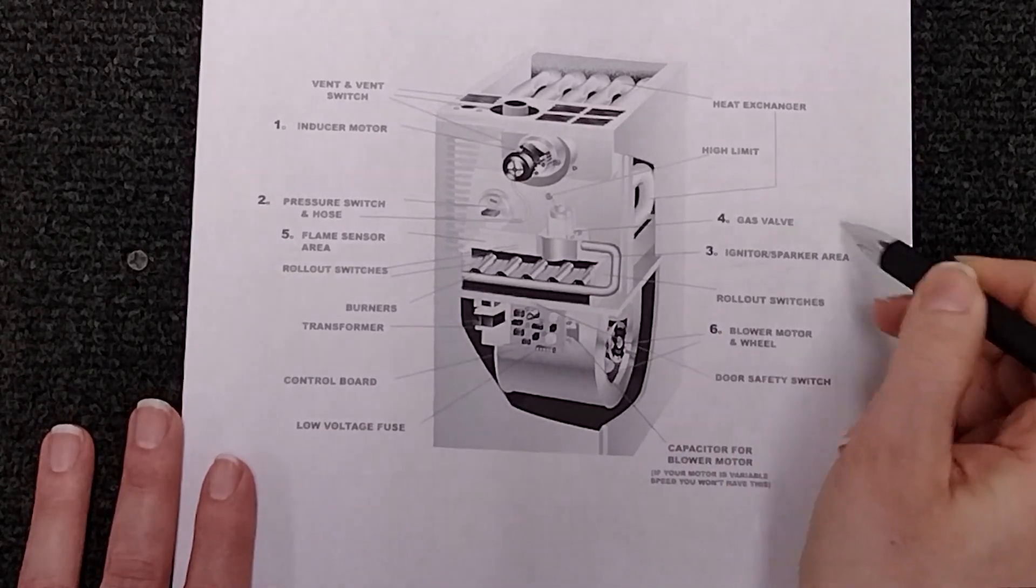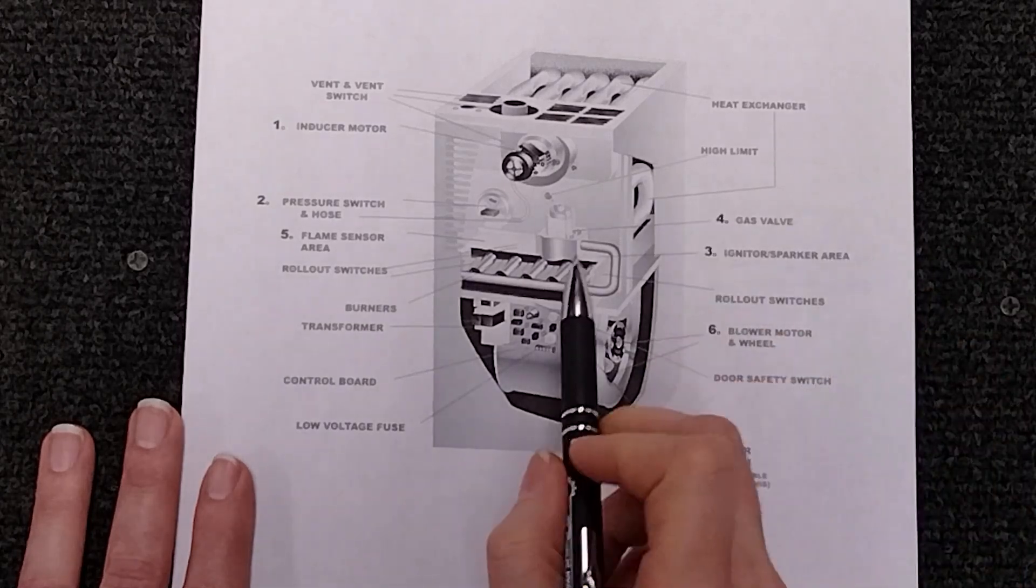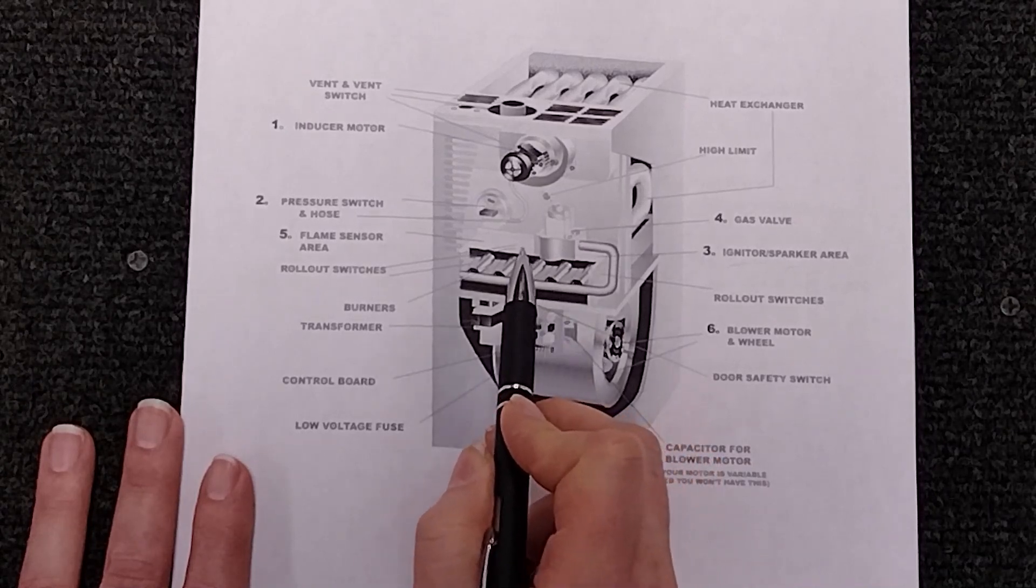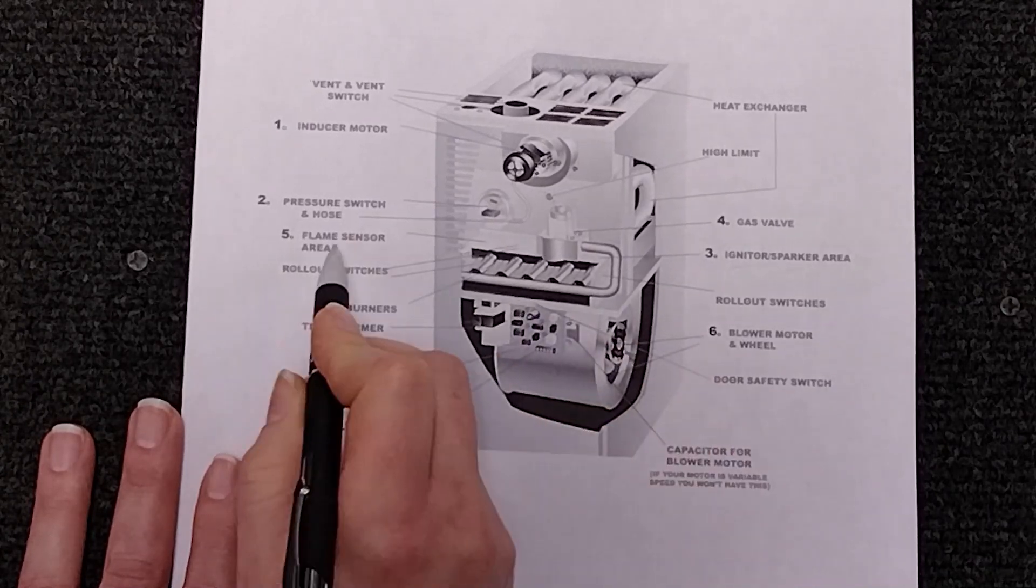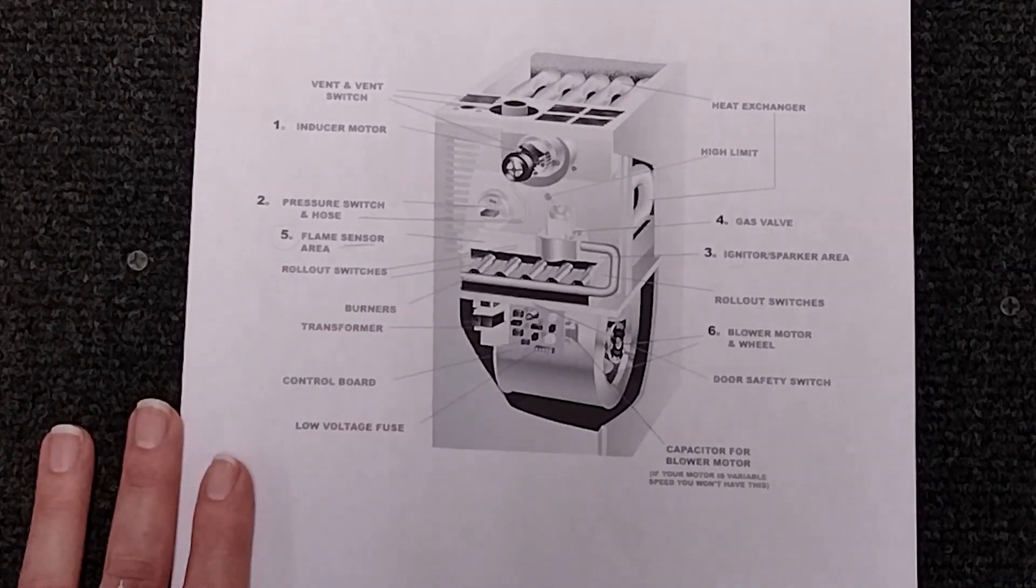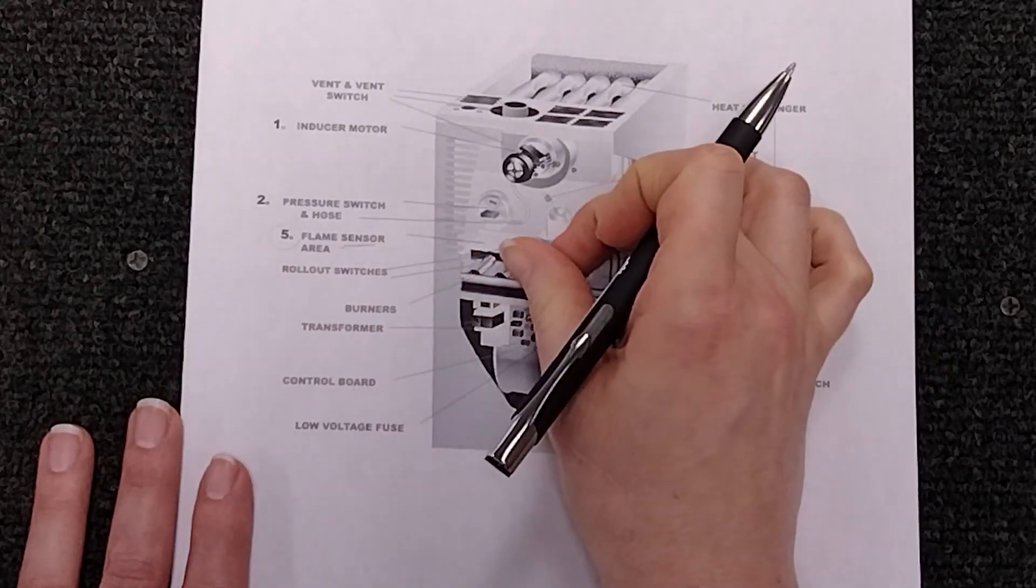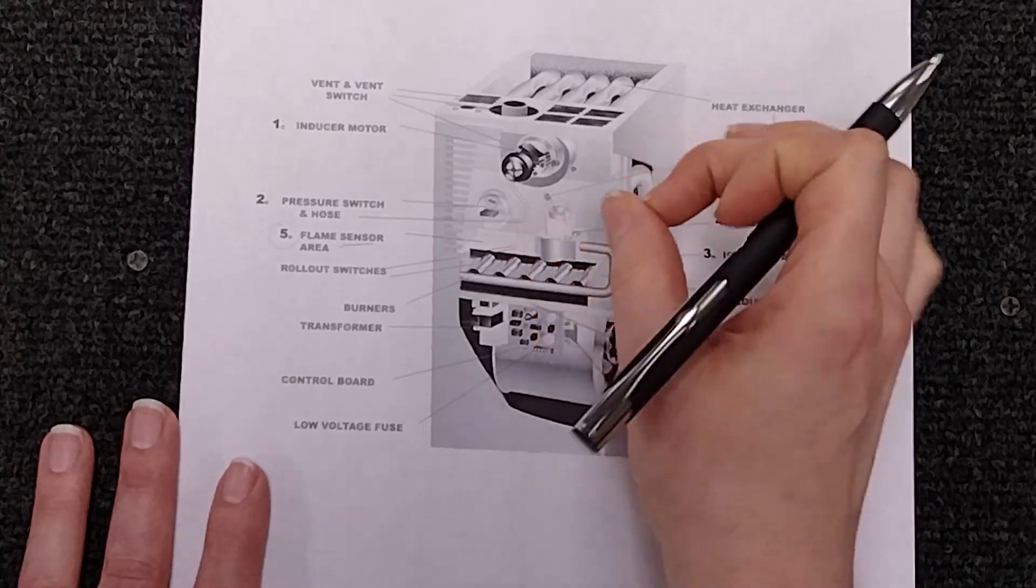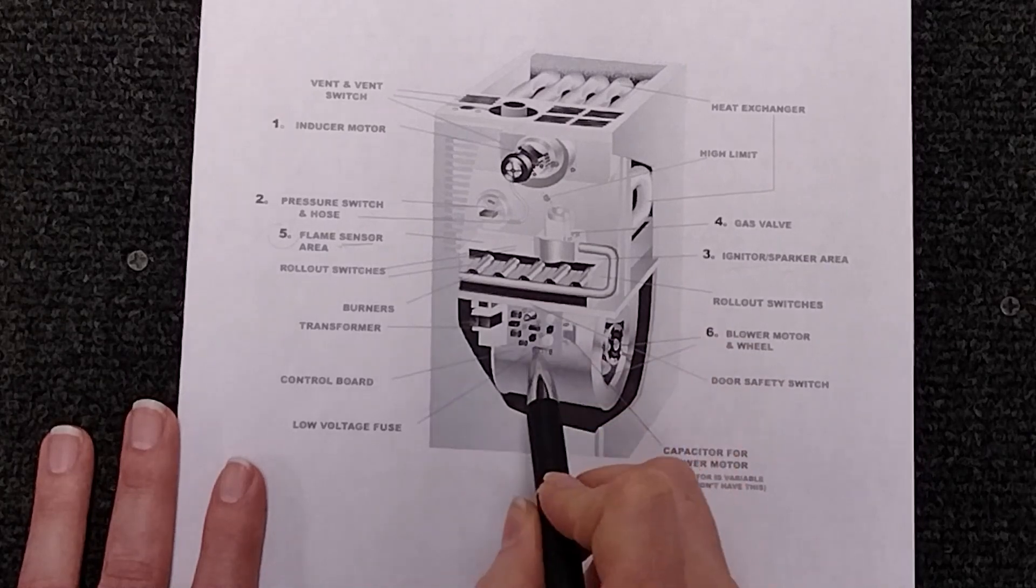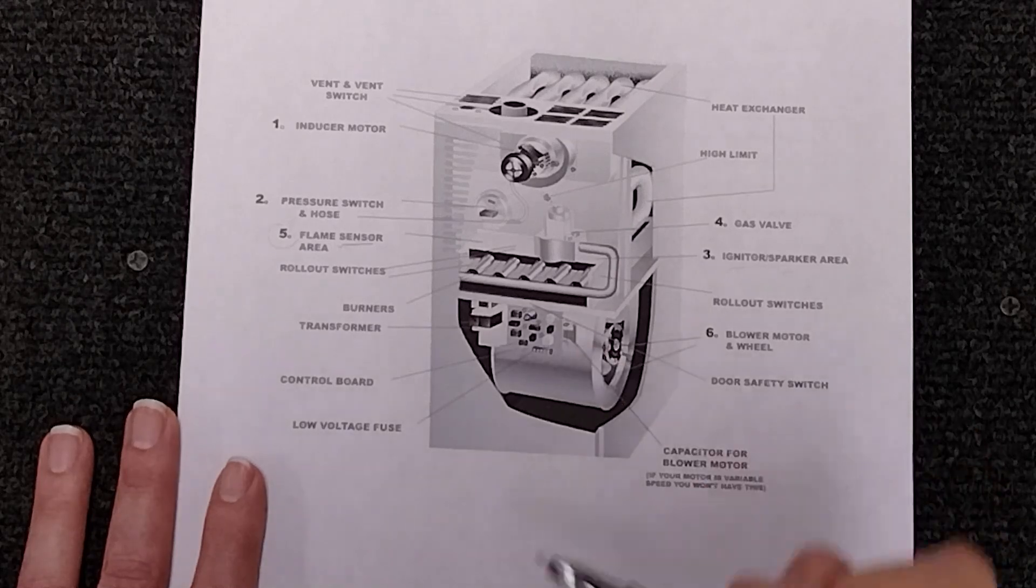So from there as we said after the igniter lights the gas valve comes on stays open and lights. Next we go over to it's going to light up go all the way across those burners to your flame sensor and there's some really cool science behind flame sensors but we'll get into that later. Just know that the flame sensor is going to send the tiniest millivolt back to the board and that board knows that everything is good and we're going to keep it on.